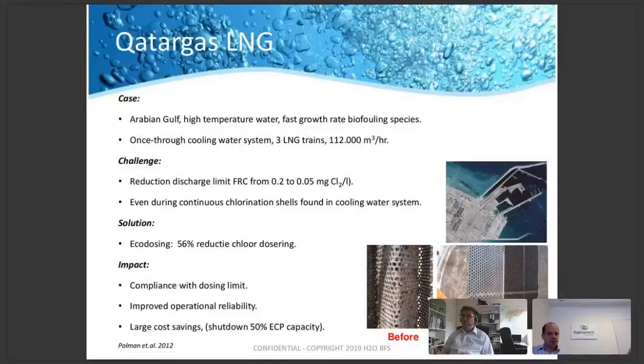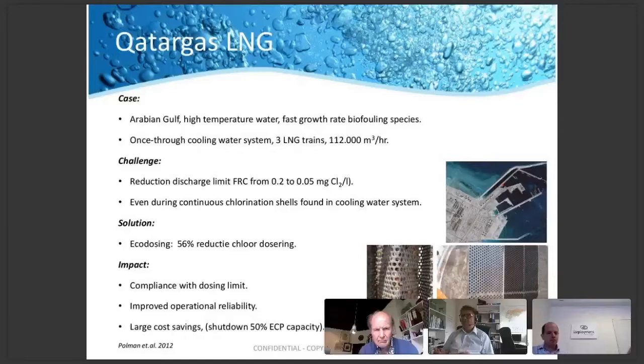We reduced the amount of hypochlorite dosing by 56%, so more than half of the amount. And as you see on the pictures on the right, the system became far more clean. The effect of hypochlorite dosing increased while you reduce the amount of hypochlorite dosing at the intake. This resulted in high cost benefits for Qatargas, but more important, compliance to the more strict dosing limits. In Qatar at the moment, the Ecodosing technology is an accepted methodology and a proven technology for the Ministry of Environment.